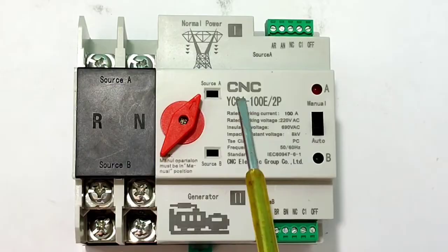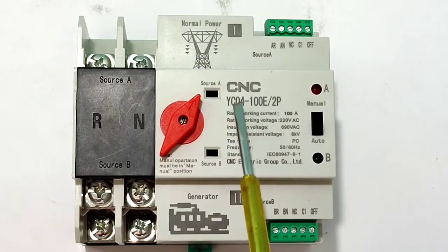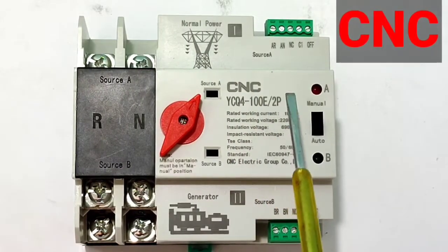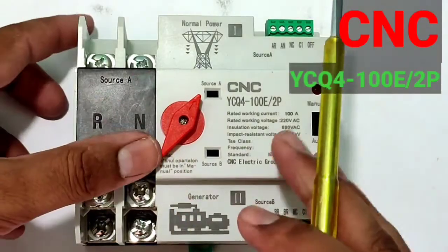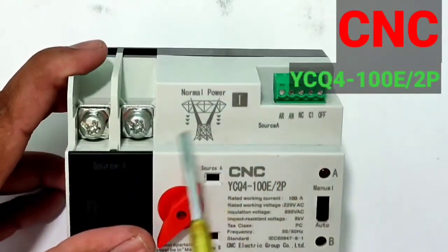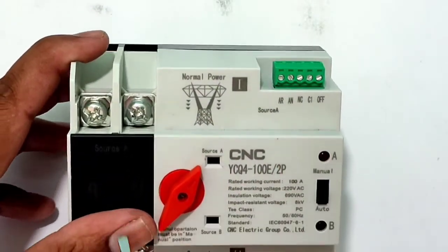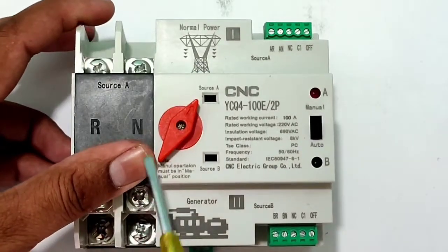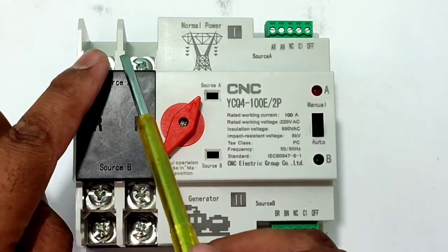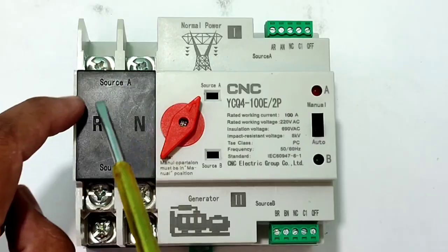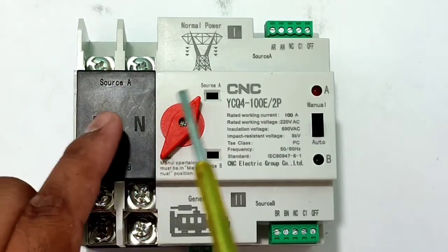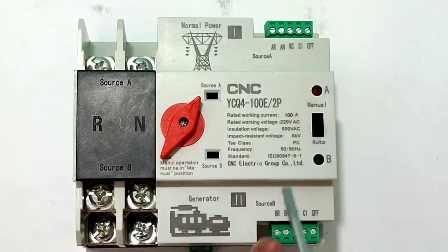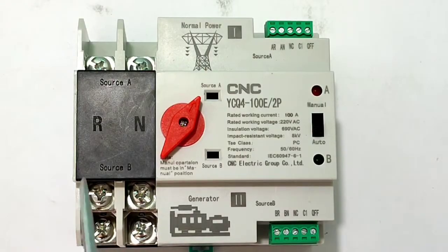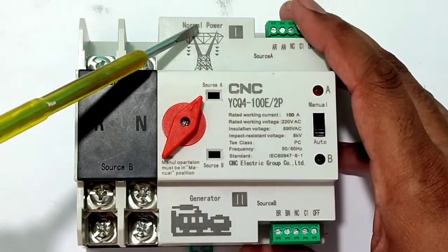This automatic transfer switch is made by CNC company, whose model number you can see on your screen. Now you can see these are the automatic transfer switch power terminals, in which you need to connect a power supply, which could be main power supply, generator power supply or solar panel supply. These are the power terminals, and these are the control terminals by which your automatic transfer switch works automatically. So this is your control terminal.